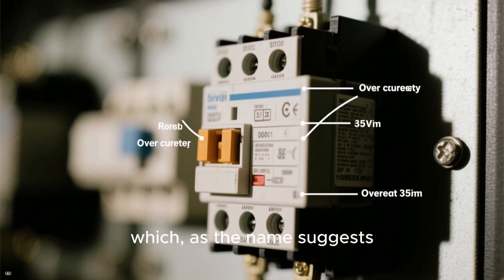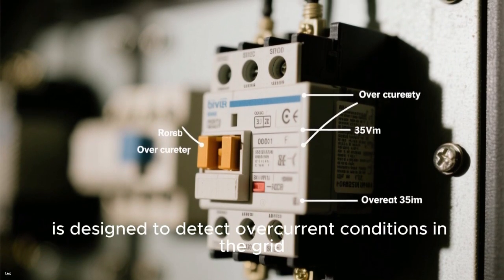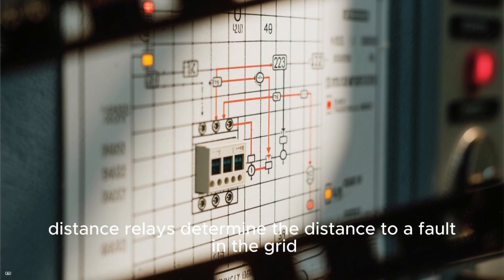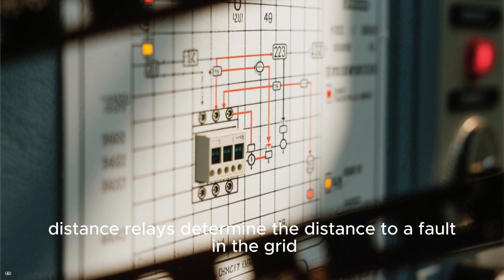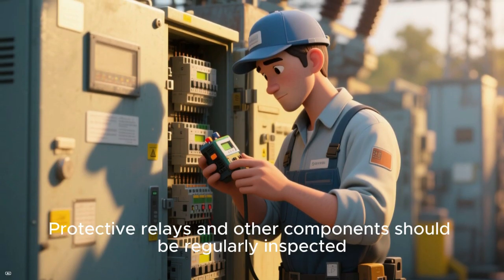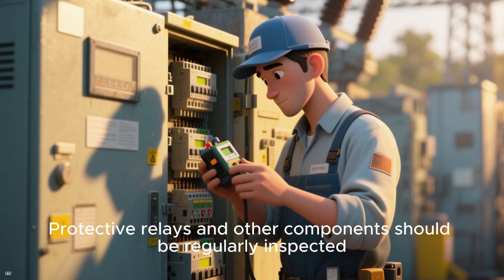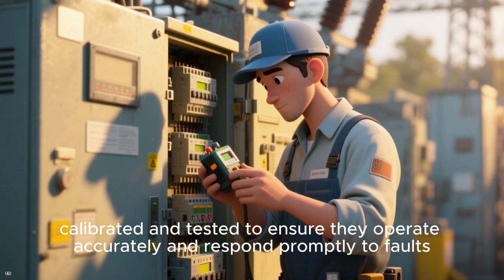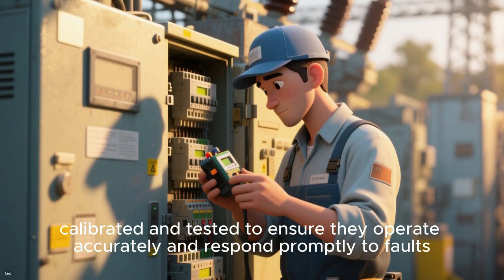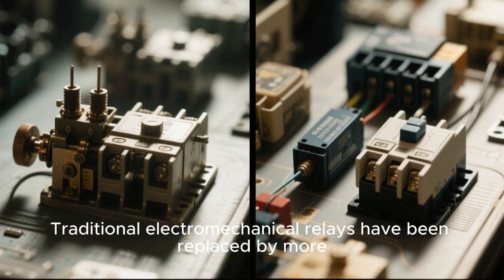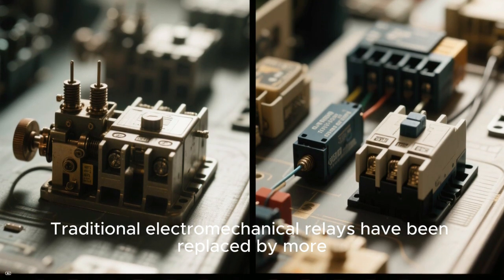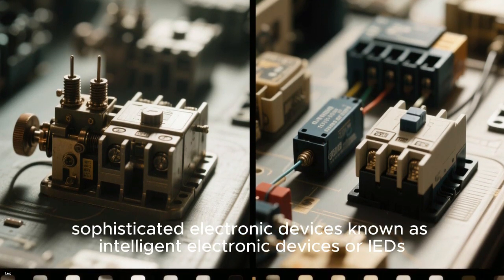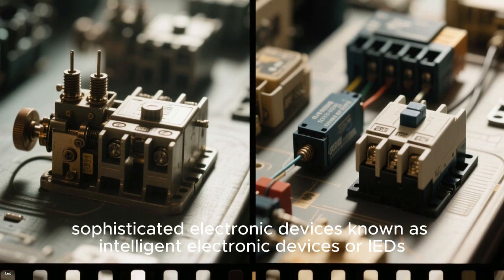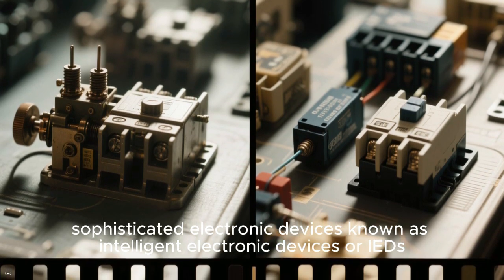One common type is the overcurrent relay, which, as the name suggests, is designed to detect overcurrent conditions in the grid. As the name implies, distance relays determine the distance to a fault in the grid. Protective relays and other components should be regularly inspected, calibrated, and tested to ensure they operate accurately and respond promptly to faults. Traditional electromechanical relays have been replaced by more sophisticated electronic devices known as intelligent electronic devices or IEDs.